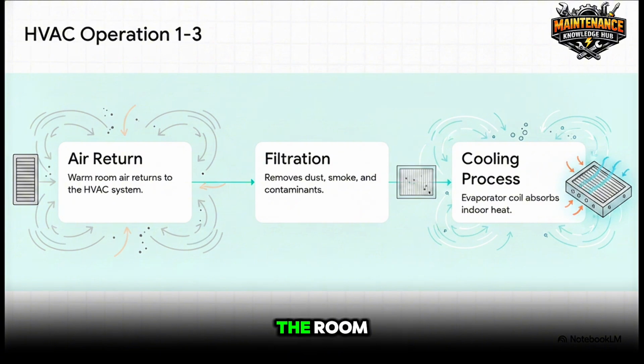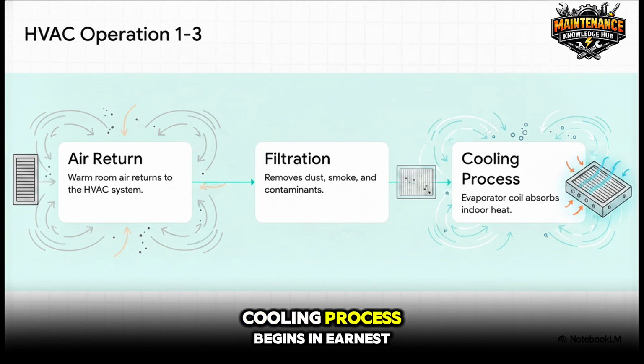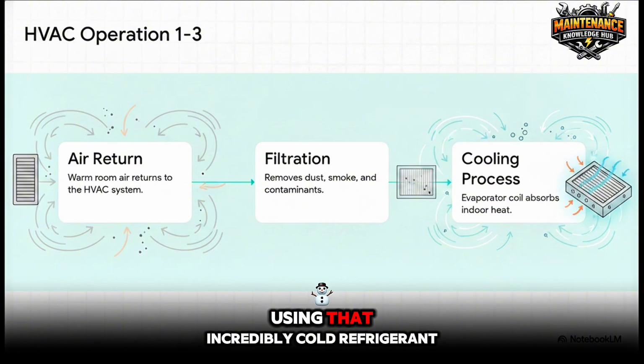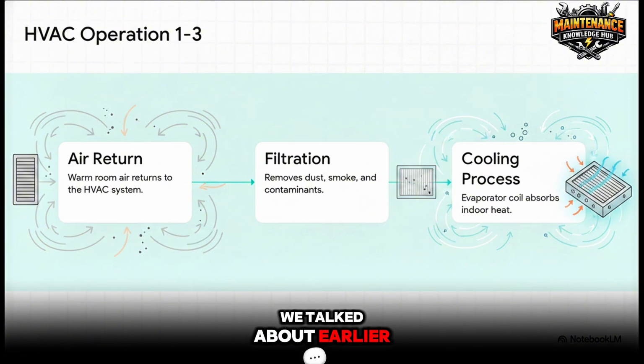Warm, stale air from the room is pulled right into the system through the return ducts. Then, in step 2, filtration, that air gets scrubbed clean. It passes through filters that capture dust, smoke, and other annoying indoor contaminants. By step 3, the cooling process begins in earnest. This freshly filtered but still warm air blows over the evaporator coil, which absorbs the indoor heat using that incredibly cold refrigerant we talked about earlier.